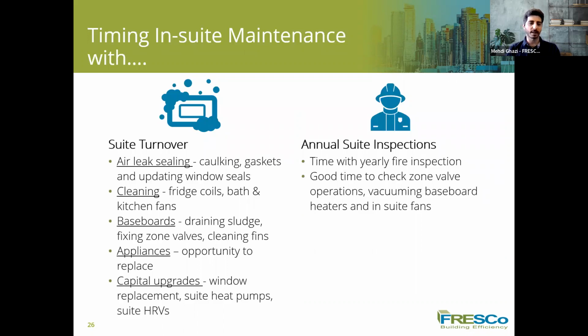One good time for doing this type of maintenance is suite turnover, which is a very good time to check for air leaks and clean the coils and bath and kitchen fans and baseboard heaters. If we need to replace any appliances or do other maintenance, we can also check our zone valves, whether they're stuck fully open or stuck fully closed. Suite turnover is the best time, as well as our annual suite inspection for the fire system. That is also a good time to do crucial maintenance like checking the zone valves and vacuuming the baseboard heaters, as well as the suite fans.